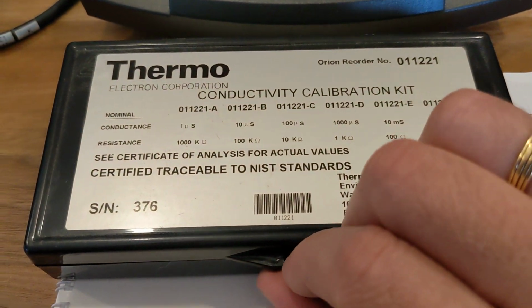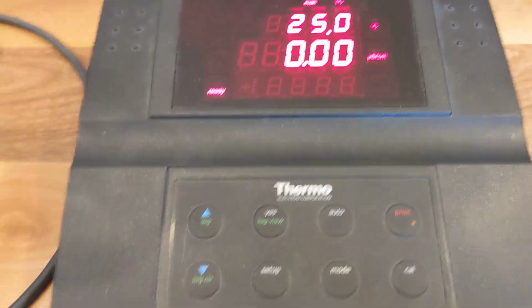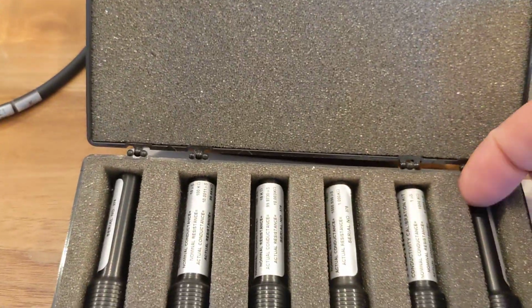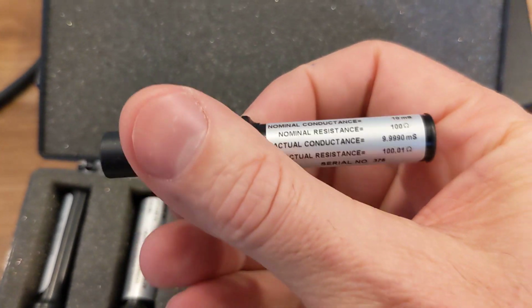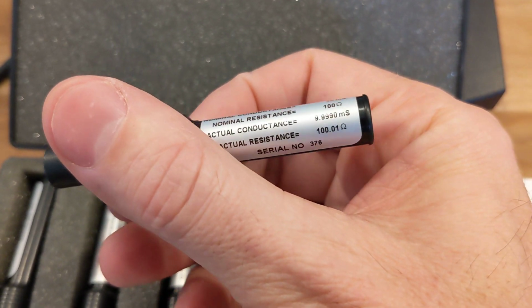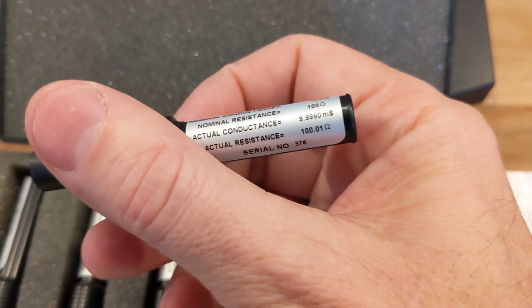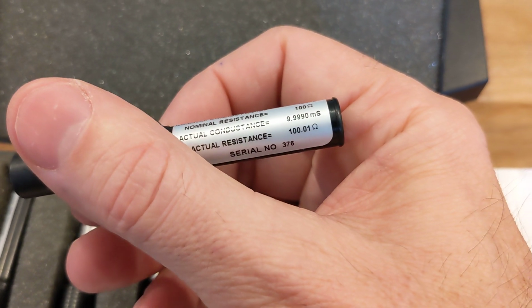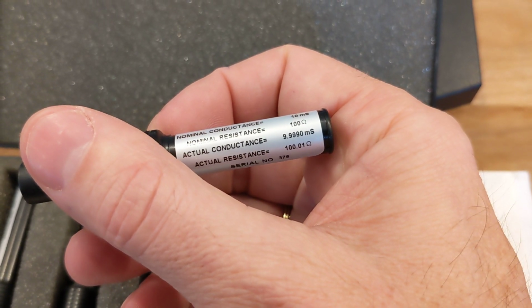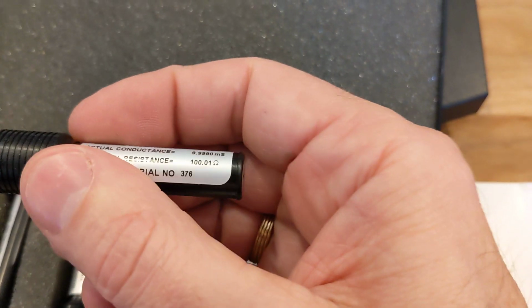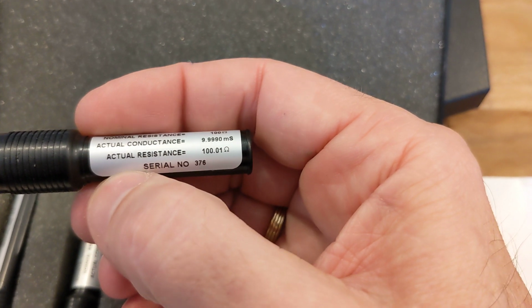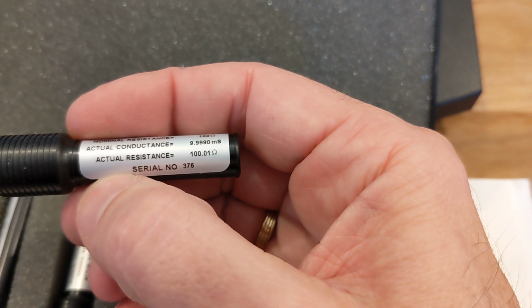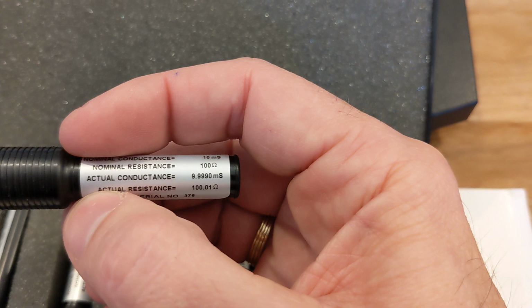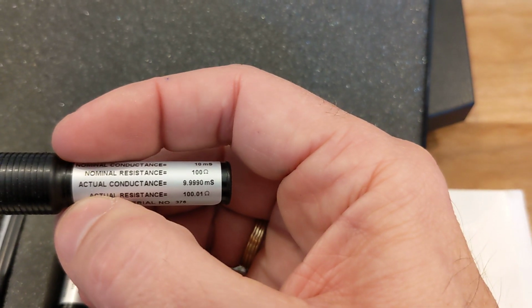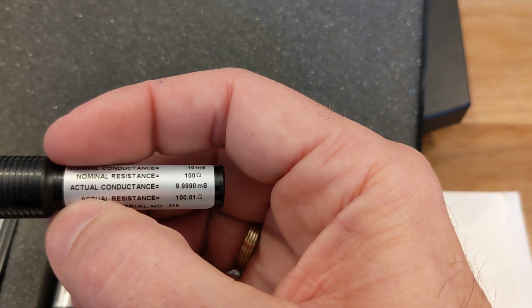So here is the conductivity calibration kit. Here's the meter. The idea, of course, is you take one of these calibration standards and you plug it into the back of the meter, and it does two things. It adds a temperature resistor to pretend to show a temperature, and then it also adds a high precision resistance to show conductance. And you can see from the label, this resistor worked out to be 100.01 ohms, which the inverse works out to 9.990 millisiemens.